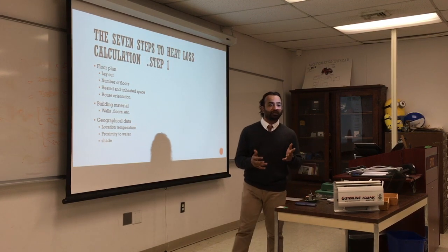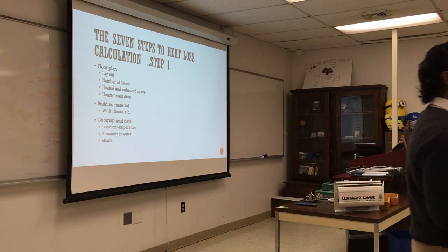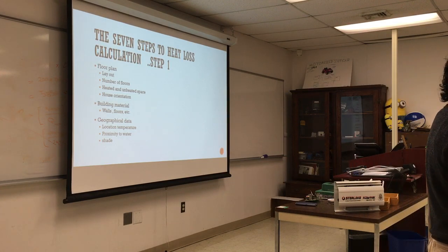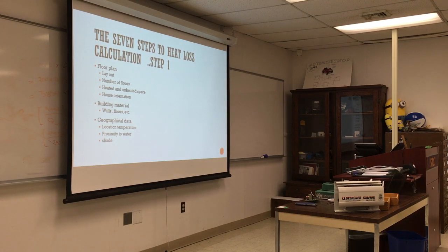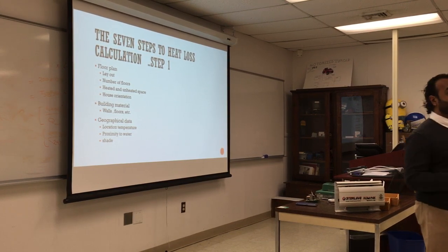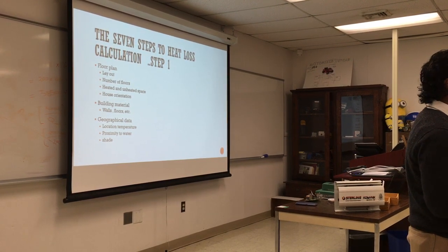And you saw from last semester, what was the average BTU for the house? 50, 60. It was from 50 to 100 actually, depending on the material. That is a lot. That was acceptable at some point, but it's not acceptable anymore. Now we want something around 30 to 25 BTU per hour. Because think about it, this is how much BTU you have to pump into the house every hour.